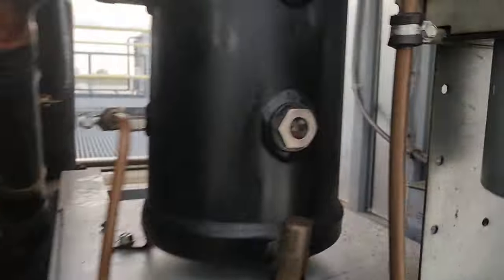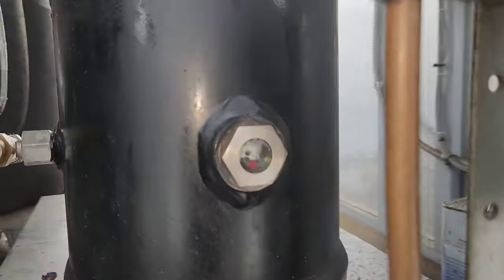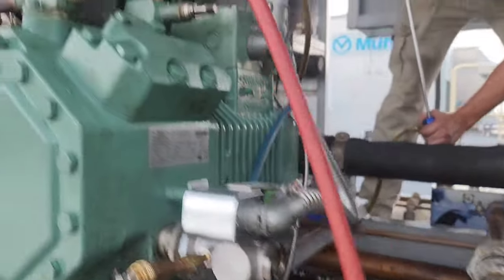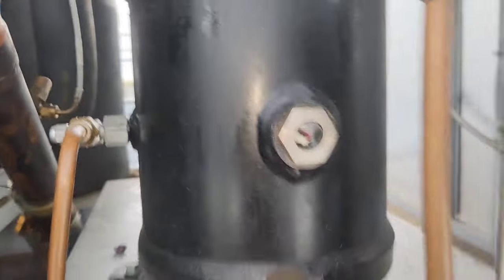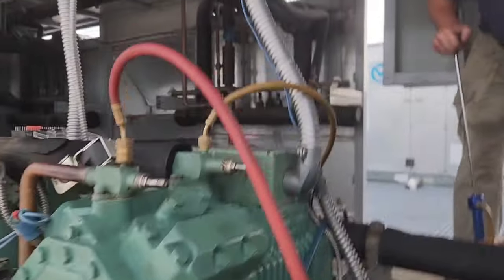Got oil? Oh shit, this thing ain't got no oil. So yeah, we gotta add oil — forgot about that. Alright, I've got my man pumping over there. Oil's going up in that one. Wait until that comes up — just put the whole gallon in it. Balls rising over here, it's going up. We're pumping directly into the suction line of the compressor.